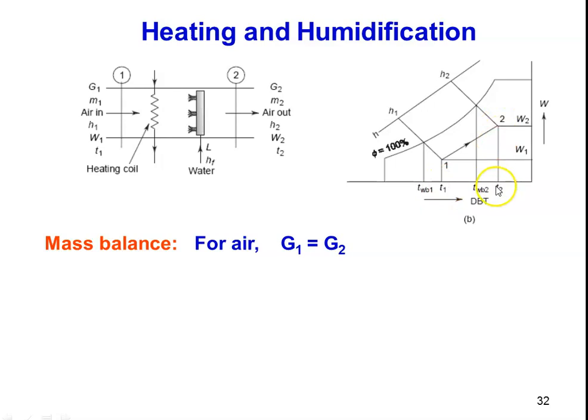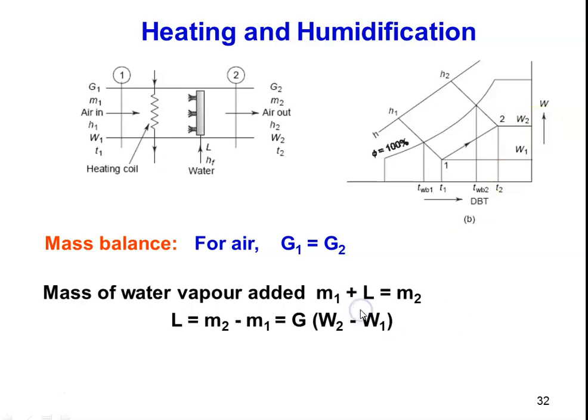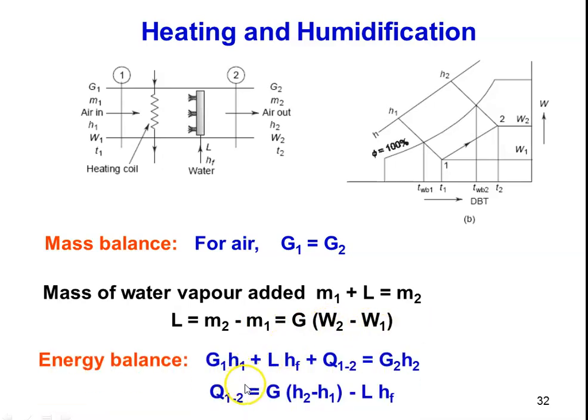T1 and T2 are the inlet and outlet temperatures; W1 and W2 are the specific humidities. For mass balance: G1 = G2 for air; M1 + L = M2 for water vapor, so water vapor added L = M2 − M1 = G·(W2 − W1). Writing the energy balance: G1·H1 + L·HF + Q = G2·H2, so heat added Q = G·(H2 − H1) − L·HF. This gives the amount of heat added and water vapor added during heating and humidification.